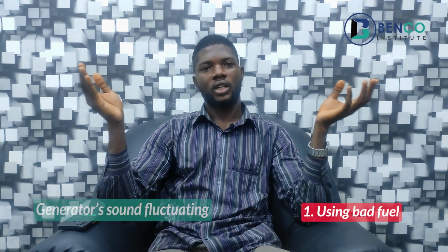Okay, these are the reasons your generator would fluctuate. One of them is using a bad fuel. A bad fuel would come from the petrol station. A bad fuel could equally come from your end. If you have a generator and perhaps you use gallons to go get this fuel and your gallon is dirty, in fact, that will contaminate the fuel. And when eventually this fuel gets into your carburetor, it affects your carburetor and stops the generator rather from having smooth running. So in order to avoid this, make sure you get fuel from the right petrol stations. Make sure you equally use the right medium for buying your petrol. Make sure your gallon is clean, and as such, your generator, I tell you, will not fluctuate.